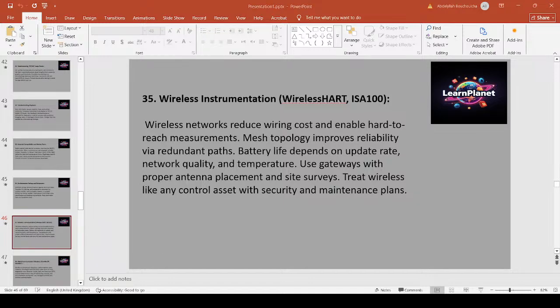Wireless reduces cable cost and enables measurements in hard-to-reach places. However, network planning, site survey, gateway placement, and antenna selection are essential for reliability. Mesh topology provides redundant paths. Battery life depends on reporting rates and environmental temperature. Treat wireless devices as control assets: secure, maintain, and back up device states. Use wireless for monitoring non-critical variables or where wiring is impractical, and consider hybrid wired-wireless designs for critical signals. Example: deploy WirelessHART vibration and temperature sensors on remote spans where cabling would be expensive. Schedule periodic battery and connectivity checks.